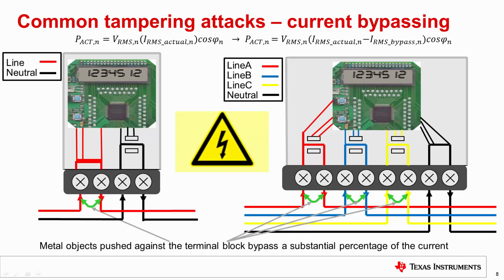A very common method to tamper with a meter is to place a metal object between a particular phase's line in and line out terminals, as shown by the green arrows in the pictures. This metal forms a current divider with the current sensing circuitry, which leads to the metal object bypassing current so that the sensing circuitry senses less current than what is actually consumed, thereby reducing the active power readings and total cumulative energy readings. In addition, there is a risk to the tamperer because of the potentially harmful mains voltage when the tamperer tries to connect the metal, as well as afterwards if the metal is exposed.